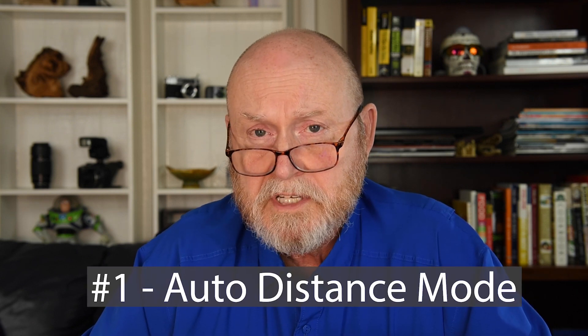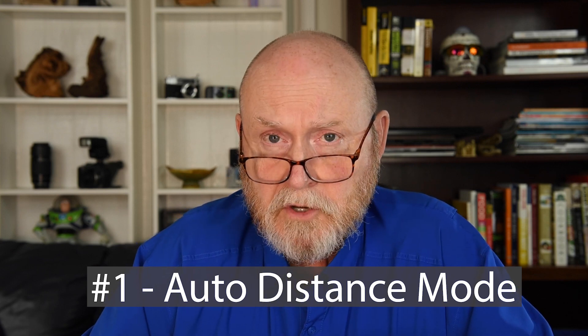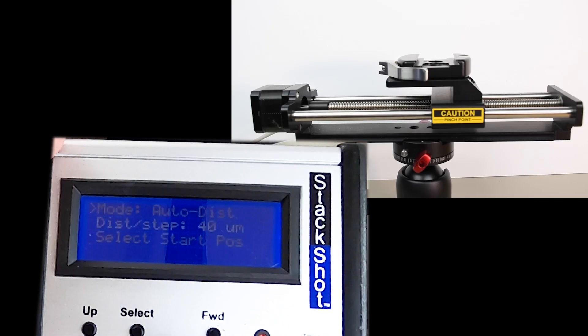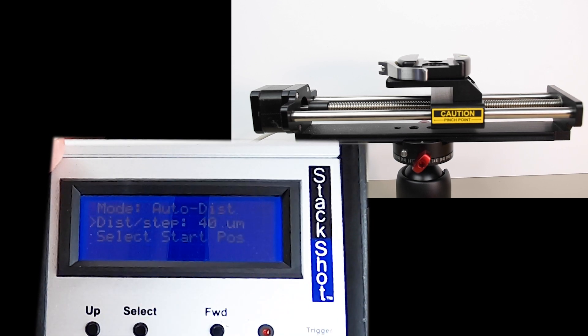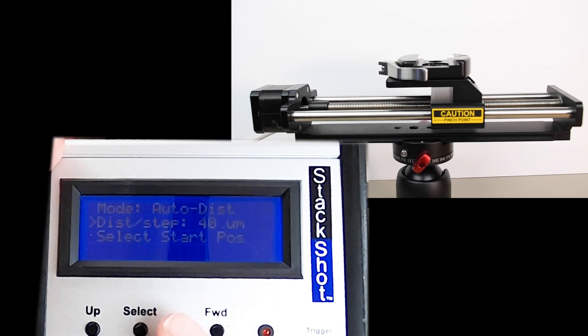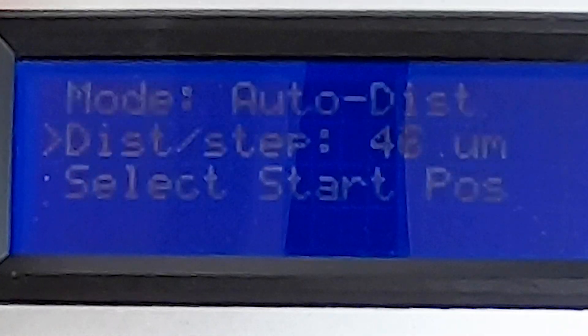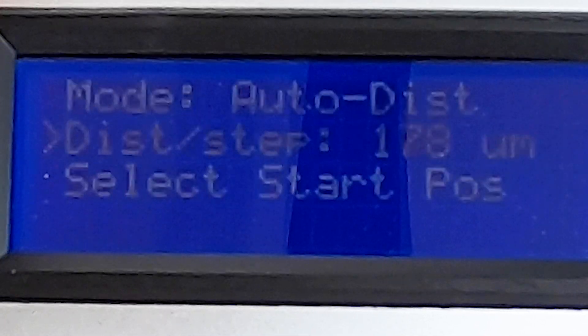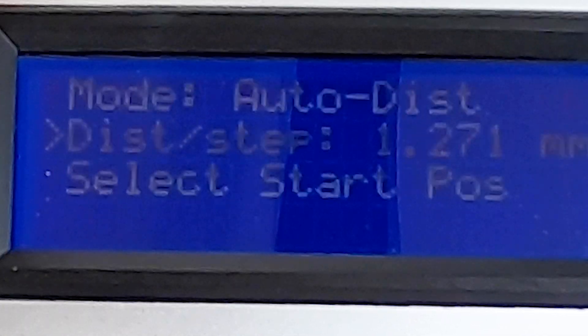The first, best, and most obvious way to use this device is in auto distance mode. The reason is because in auto distance mode you set the step length in microns. You also set the position that the stack begins and the position that it ends. So in auto distance we'll use the select button to set our step length — let's increase it to about a millimeter.